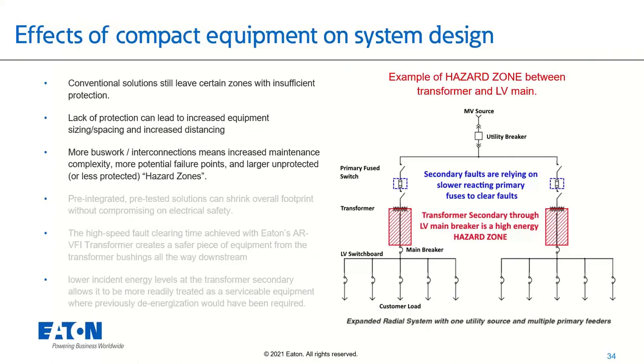So just to give one last highlight, I know we're getting a little bit short on time, and I do want to have just a few minutes for question and answer. The bulk of what I want to get across to you today is that those primary devices alone, if you're relying on just that primary fuse or that primary vacuum interrupter, are going to create this hazard zone between the low voltage of the transformer and the low voltage main breaker.